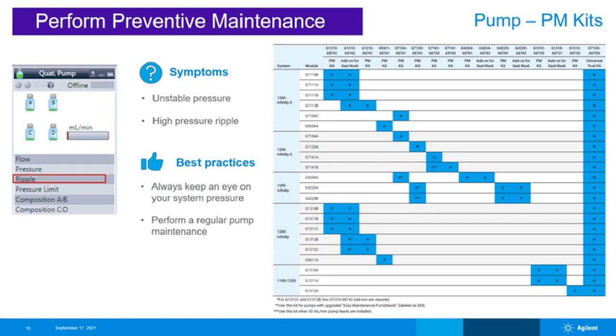The pressure ripple can be monitored, and this is a useful diagnostic tool. If you are pumping the same mobile phase composition on an equilibrated system, the pressure ripple should not fluctuate widely. If there is excessive pressure ripple, there may be an issue with the pump. Looking at the behavior, whether it's rhythmic or erratic, and how large the fluctuation is, will drive the troubleshooting in a specific direction.